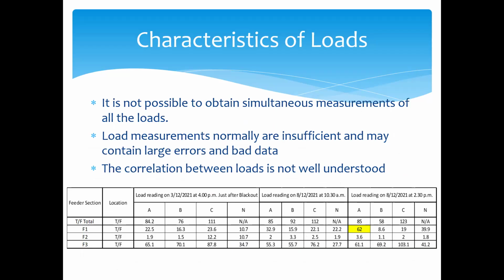The other thing is, if we consider obtaining measurements of load in a distribution network, it's not possible to obtain simultaneous measurements of all the loads. Further, those load measurements are normally insufficient and may contain large errors and bad data. The correlation between loads is not well understood. To give you an example, these were some values we obtained during load balancing of a transformer. Even though it is difficult to balance the load, we try our best to balance the load in distribution transformers to reduce power losses and improve voltage profiles for the customers.